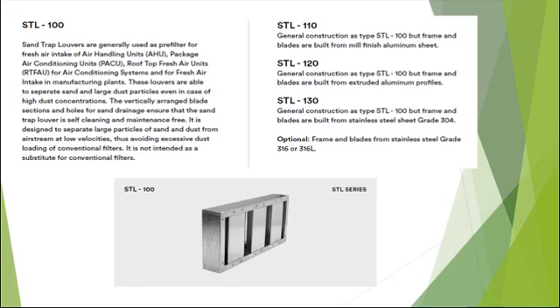The construction standard for sand trap louvers uses galvanized steel sheets: the frame is gauge 16 and the blades are gauge 18. It comes with a steel bird screen of 12 by 12 by 1 mm fixed behind the blades. The minimum neck size is 150 by 150 mm and the maximum size is 2200 by 1200 mm.